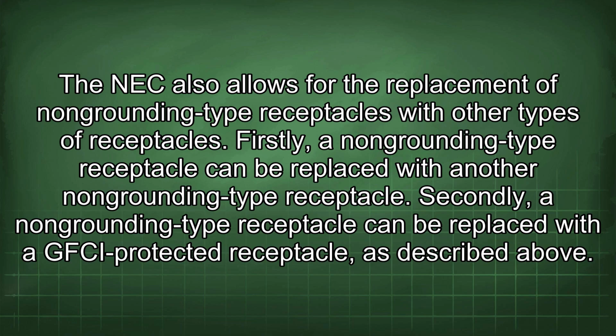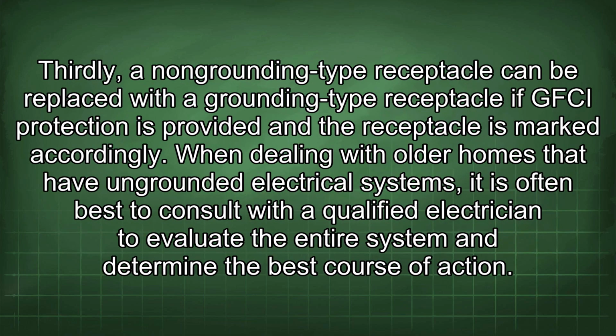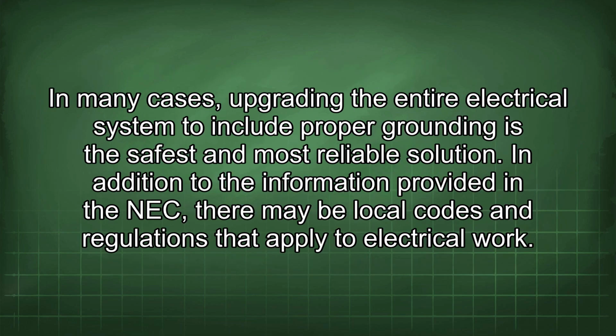Secondly, a non-grounding type receptacle can be replaced with a GFCI protected receptacle, as described above. Thirdly, a nongrounding-type receptacle can be replaced with a grounding type receptacle if GFCI protection is provided and the receptacle is marked accordingly. When dealing with older homes that have ungrounded electrical systems, it is often best to consult with a qualified electrician to evaluate the entire system and determine the best course of action. In many cases, upgrading the entire electrical system to include proper grounding is the safest and most reliable solution.